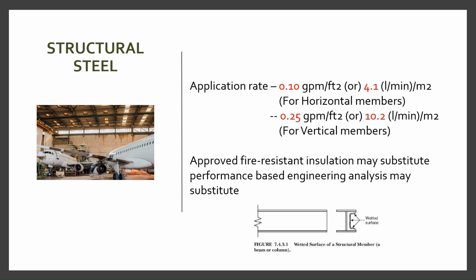Structural steel also shall be protected with a water spray system in some particular scenarios, like exposed beams to be protected, for example in aircraft hangars. This is the extract from NFPA 15. It shows the wetted surface of a structural member. Here we will place the nozzles. As per NFPA 15, many people misunderstood that protecting one side is enough, but if you look at the FM guide, we will understand the other side of the beam also must be protected with nozzles.